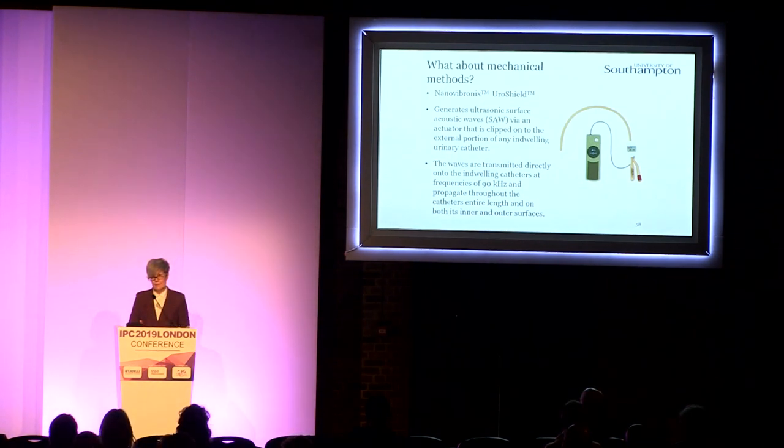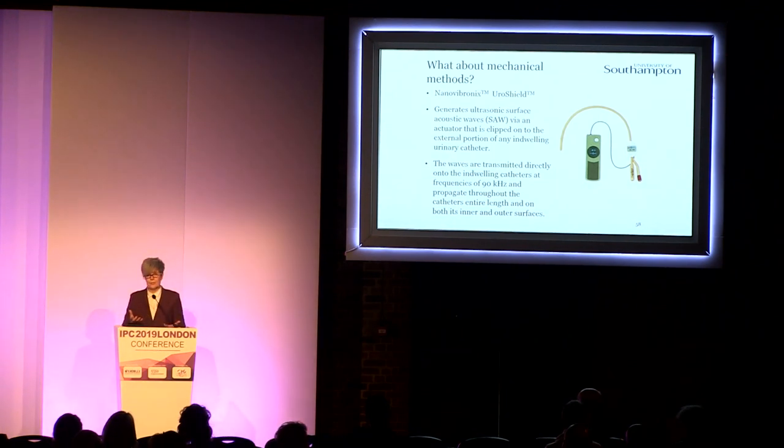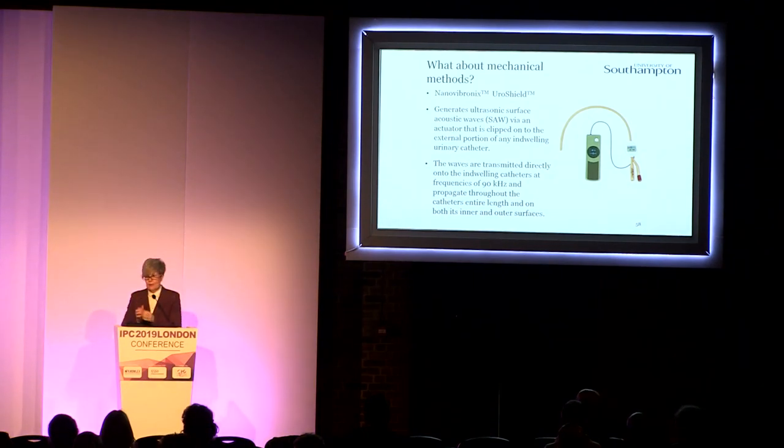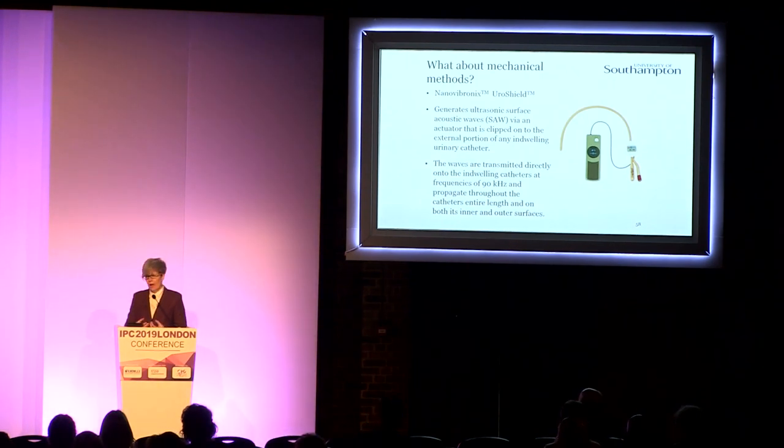What about mechanical methods? We know there are things like bladder washouts, but bacteria are very good at withstanding the shear forces against the catheter itself. While you may clear some encrustations, you've probably still got that layer of bacteria below. We've just carried out a lab study using the UroShield device. This generates a low-frequency surface acoustic wave — very low-frequency ultrasound — where the actuator clips onto the base of the catheter on the outside surface, and the waves are transmitted along the length of the catheter, both on the external surface and the internal lumen.